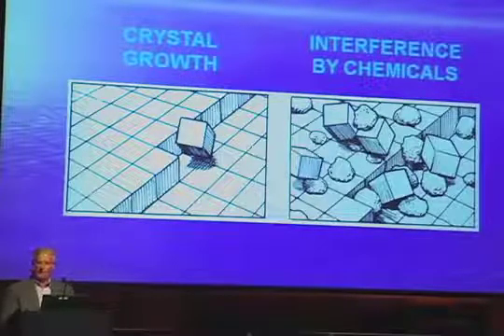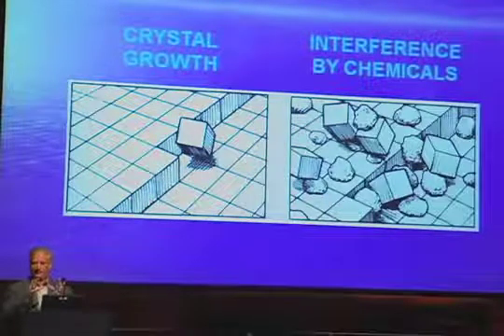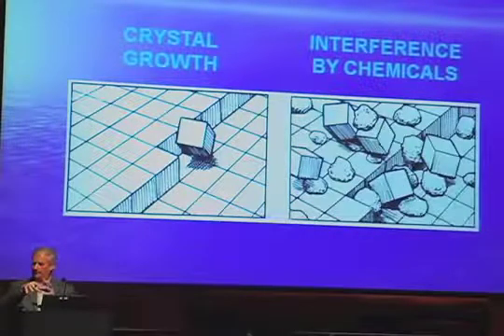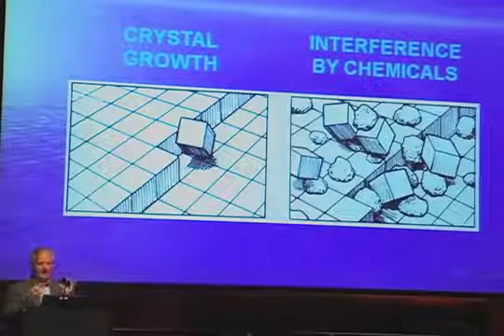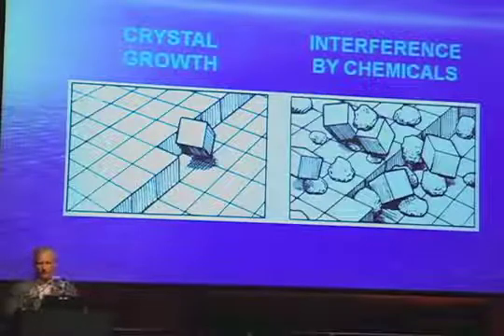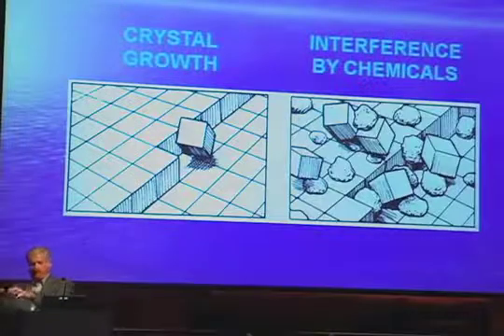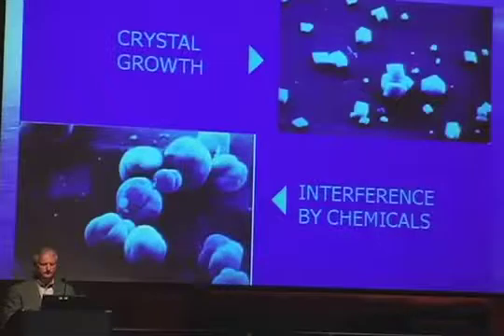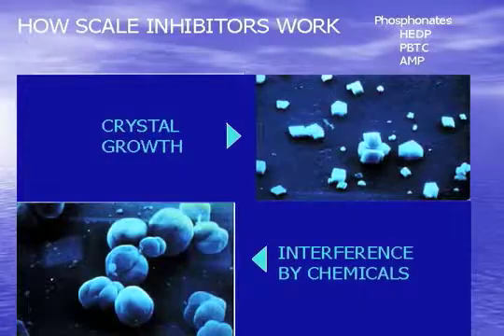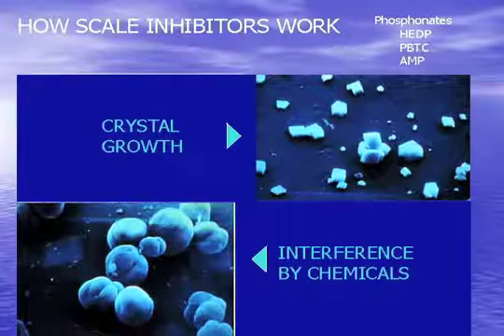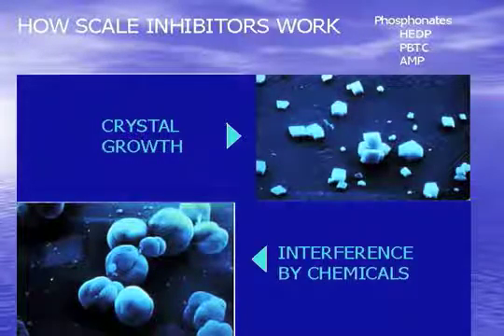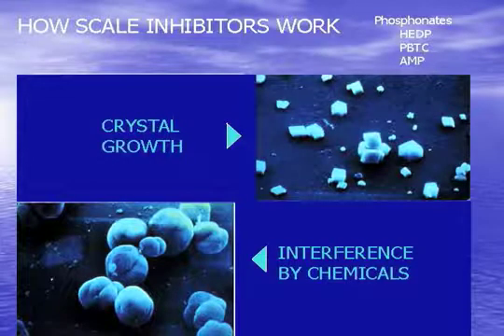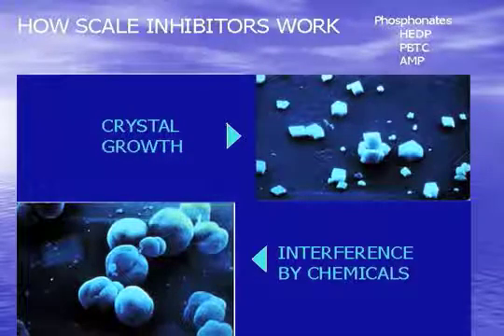What the phosphonates do is they actually modify that scale. So as calcium and carbonate come together, the phosphonates get their finger in there and they modify that crystal. Now it's not an organized crystal anymore. It's trying to find a slot for itself — can't find a slot — and eventually it gets purged out of the blowdown. It's basically a crystal modifier. When you look at it from an electron microscope standpoint, you can see the crystals that are nice cubic shapes, starting to form on top of each other. When you modify them with the phosphonates, you can see how they're all distorted — they really can't form a deposit. They run around the system and eventually either settle out somewhere or go through the blowdown.